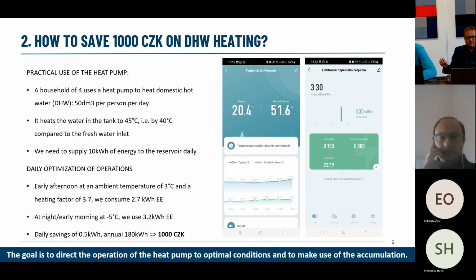And just for comparison, if you set the controller so that it heats up that water early in the afternoon, say on a typical winter day in our latitude, longitude, the ambient would be 3 degrees C above zero. The heating factor 3.7, you would consume 2.7 kilowatt hours. If you let the heat pump operate in the night or in early morning when the temperature typically hits the bottom for the particular day, so let's think of -5, you already talk about 3.2 kilowatt hours of electrical energy.